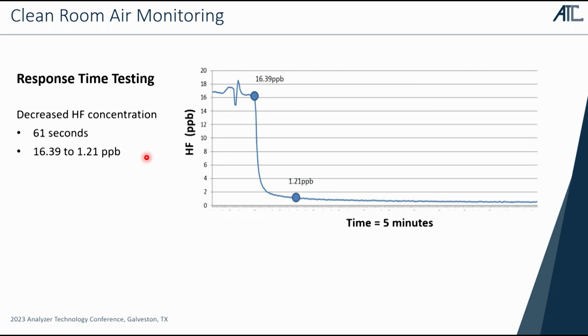For HF, and this is a huge challenge doing this in a chamber in a laboratory because it's HF gas. But they bled some HF gas into this chamber and then flooded the chamber as quick as they could with air. And of course, the exhaust of the chamber was all scrubbed. But they saw a decrease from 16 part per billion down to 1 part per billion in 1 minute. So the response time, again, not only for the process, but for air monitoring for safety and personnel reasons, it's the response time and the accuracy at low levels.